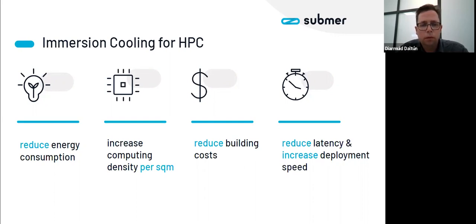We're seeing a clear direction in the increase of rack density for new supercomputers. We'll see the numbers for Summit shortly, but some of the projects we're involved with already reach 80 kilowatts per rack, which really is pushing it for air. Actually, forget about air, it's just part of the solution for these densities. Nobody deploying those densities for HPC is even considering an air-only approach, so you definitely see liquid being implemented. Quicker and cheaper deployments are a secondary benefit of the technology, maybe not so critical in national labs, but for corporate HPC deployments, building for less is key.